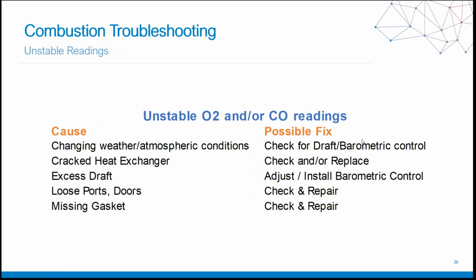Another item for troubleshooting: unstable readings. In that case, we're talking about unstable oxygen and unstable carbon monoxide. One of the things that could be the cause is changing weather or atmospheric conditions. If that's the case, we want to check the draft and/or the barometric control. As you traverse different job sites, you'll open a door to a room and it's going to feel like you've just entered an airlock, a vacuum or a suction zone. That is because of the air pressure in that space.